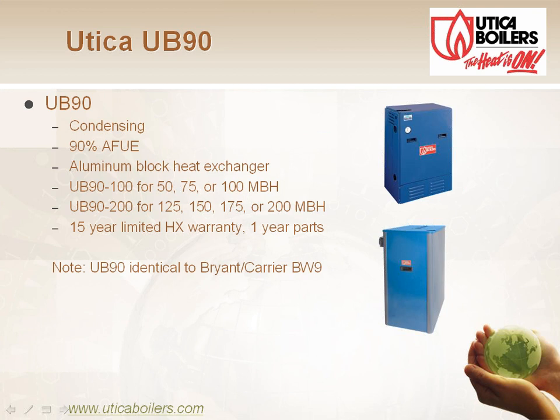It is a condensing boiler, so that's how we're getting the 90% efficiency. However, it is not a modulating boiler, so it is on-off control. So if I had a 100,000 BTU boiler, it'd either be running at 0 BTUs or at 100,000. It would not modulate in between like all the other boilers I showed you previously. Okay?